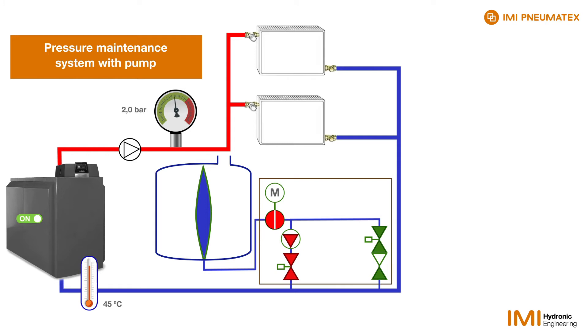A dedicated controller detects this change in value and opens a motorised valve so the water can escape into the vessel and the pressure can drop again. The vessel is filled until the pressure drops down to 1.7 bar, then the valve closes again.